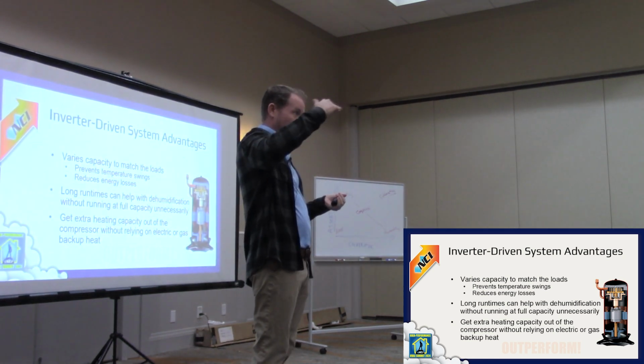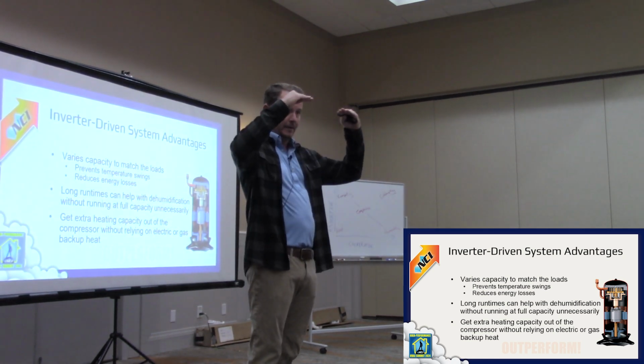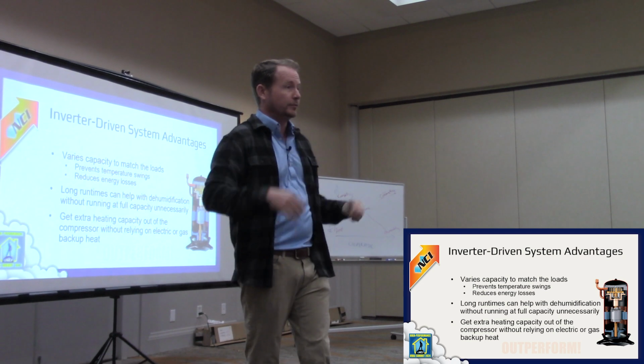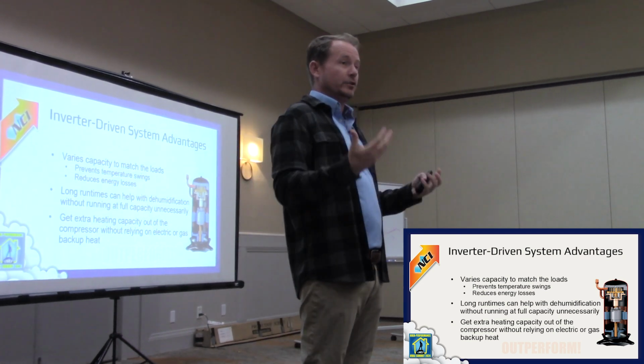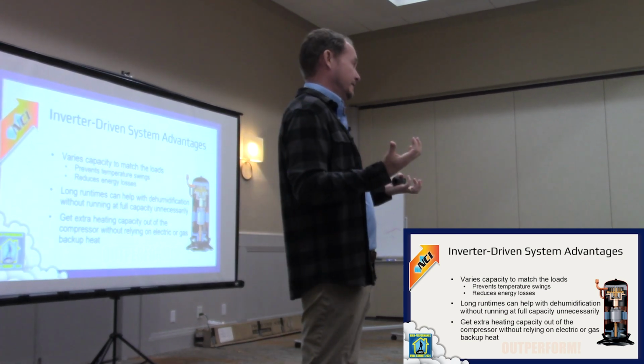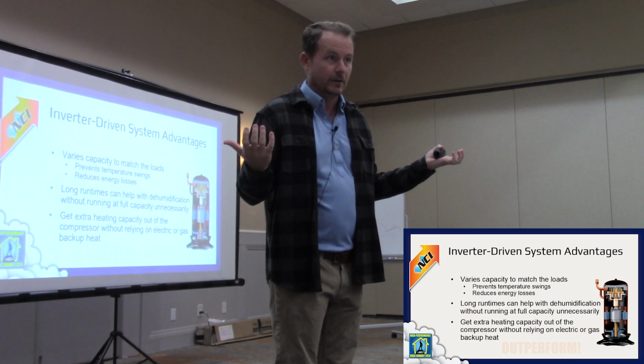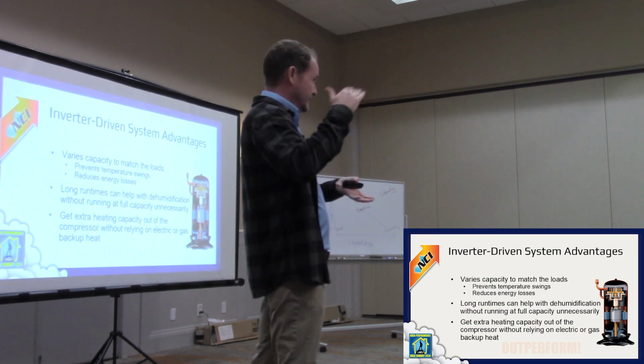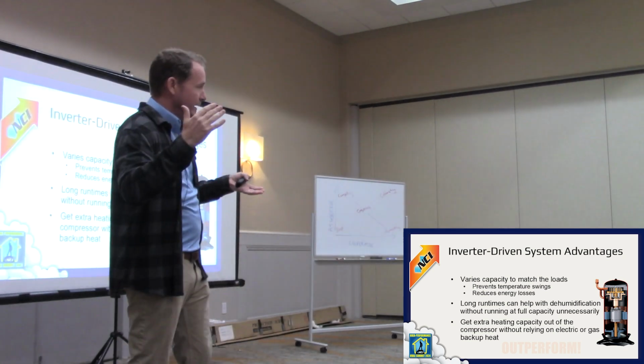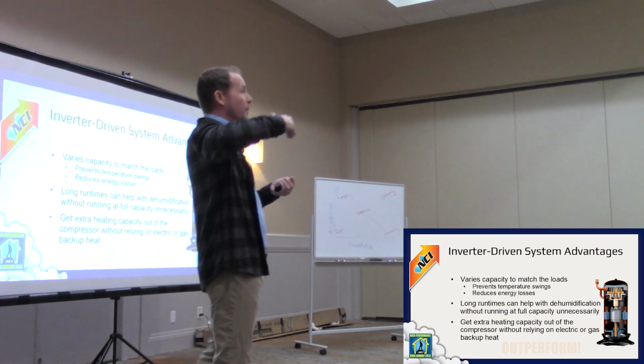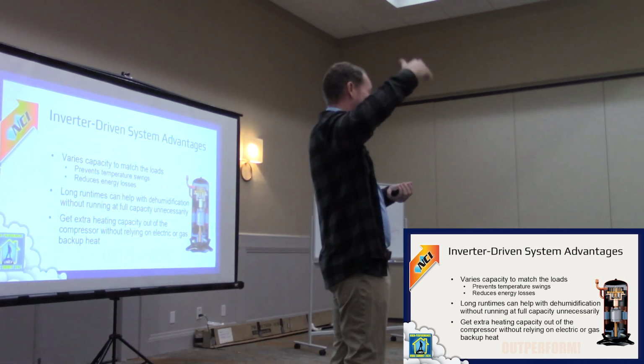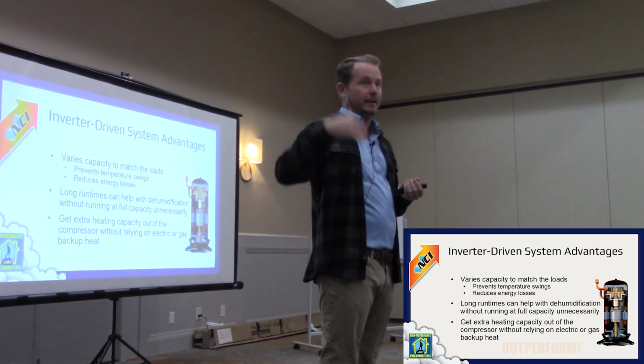Get it turned down to where it's right at about set point, and then throw your probes on it, look at Measure Quick and see how it's doing on latent. And that's sensible heat ratio, right? You want to see a sensible heat ratio that's nice and low. Generally speaking, if you start seeing it creeping above 0.8 sensible heat ratio, it's not doing great.